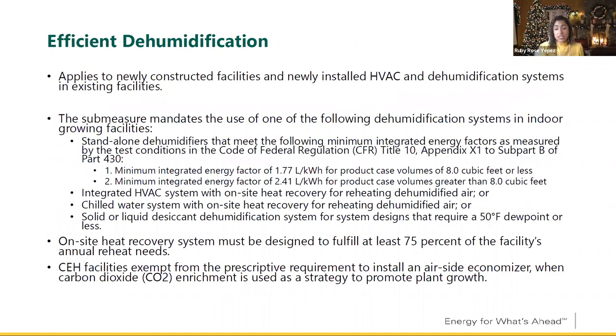Then there's also the efficient dehumidification requirement. This applies to new construction and newly installed HVAC and dehumidification systems, even within existing facilities. This measure mandates the use of one of the following dehumidification systems: either a standalone dehumidifier which meets the energy factors noted, an integrated HVAC system with on-site heat recovery, a chilled water system with on-site heat recovery, or a solid or liquid desiccant dehumidification system for system designs that require a 50 degree Fahrenheit dew point or less. Also, an on-site heat recovery design system or heat recovery system must be designed to fulfill at least 75% of the facility's annual reheating needs.